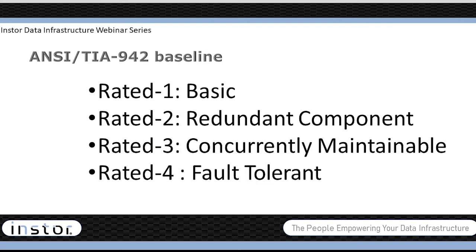So you have dual path on cooling, electrical, telecommunications, and of course, separation of the rooms and the areas. For this fault tolerance, compartmentalization is key here. Of course, very strong physical security controls, maintenance, training, monitoring, etc. So these are the differences in the 4 ratings.